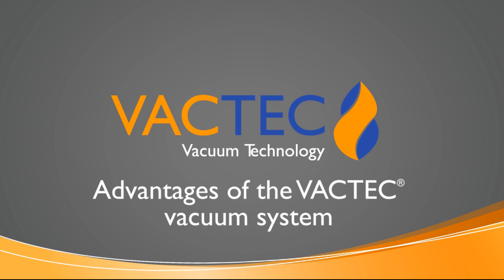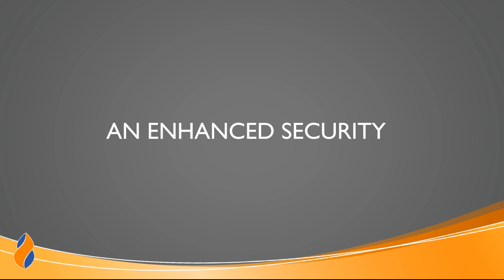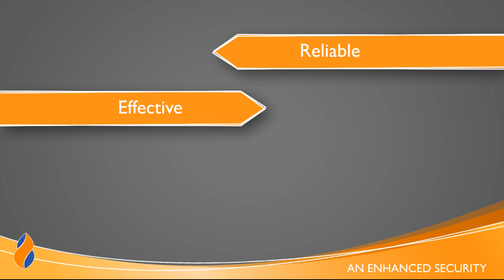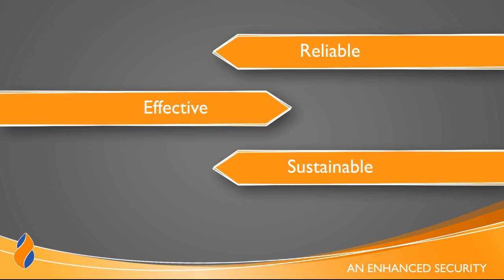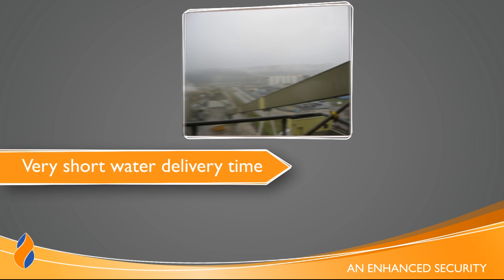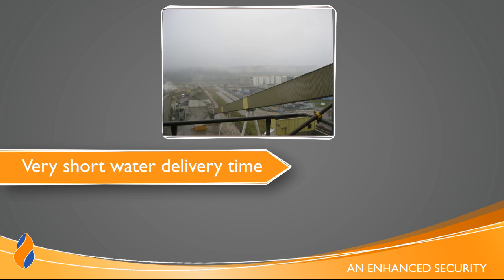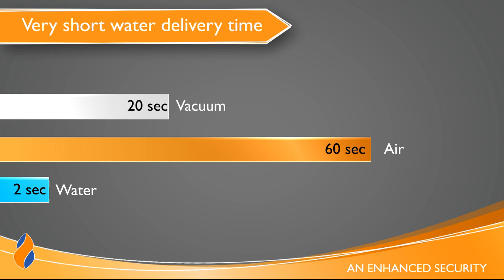The VACTEC fire protection system by Vacuum Sprinkler has been designed in order to increase the safety and the reliability of the traditional protection systems while eliminating all their drawbacks. The VACTEC system is a reliable, effective and sustainable system. Its water delivery time is very short, around a third of needed time in a dry system.